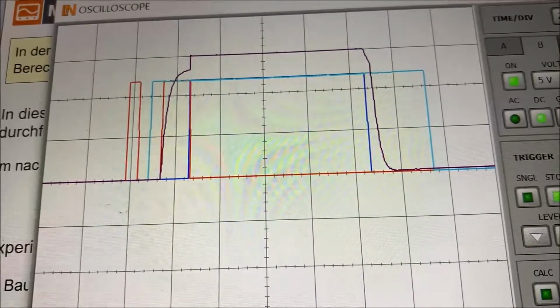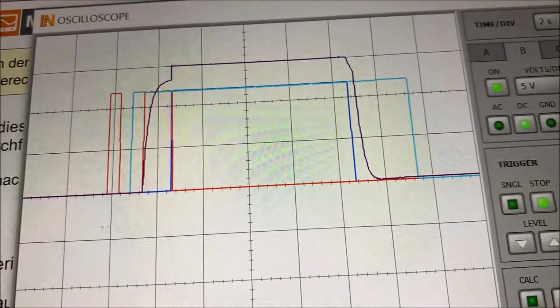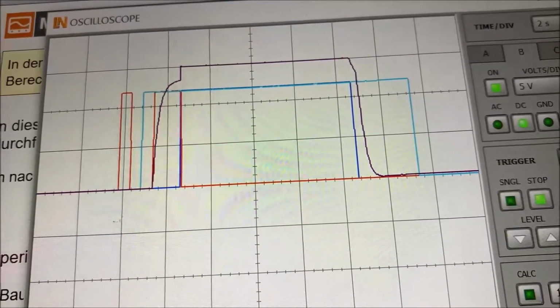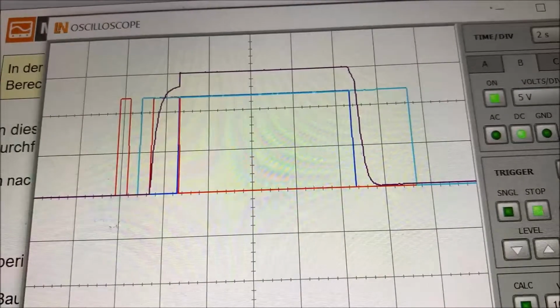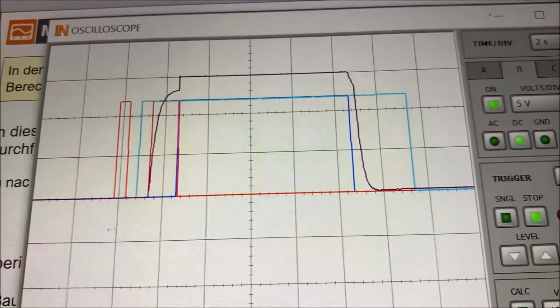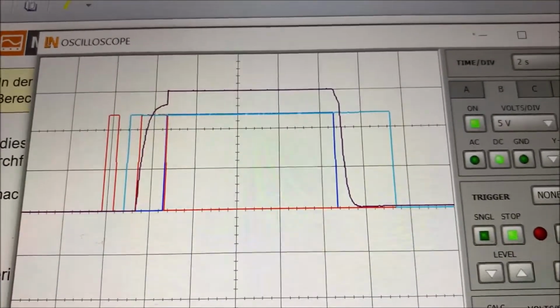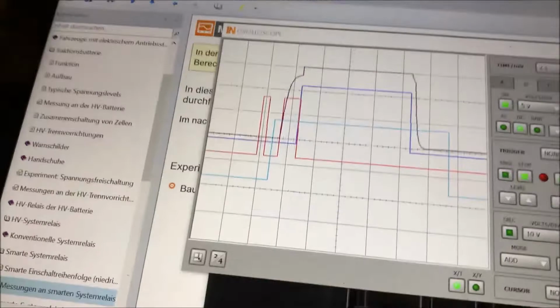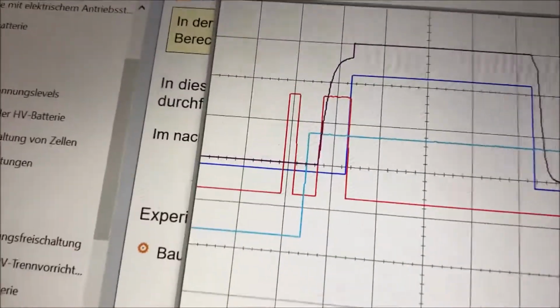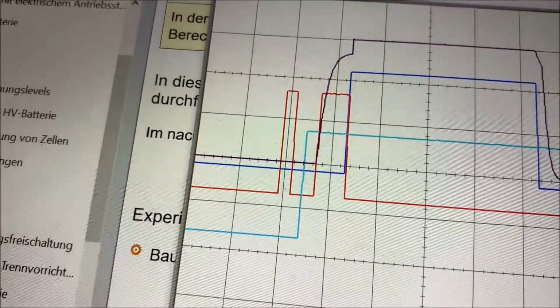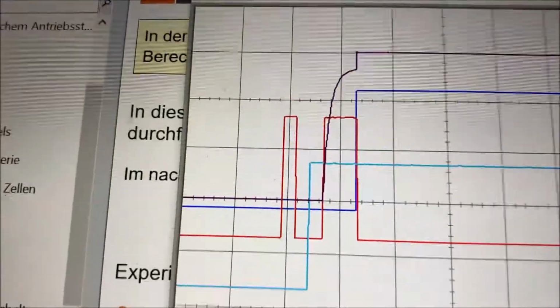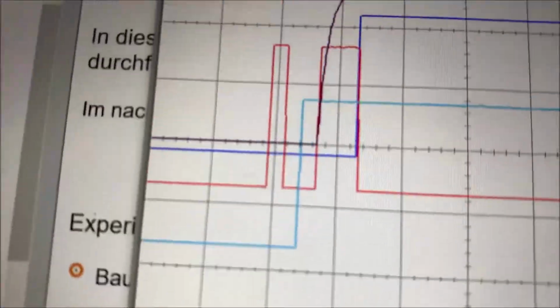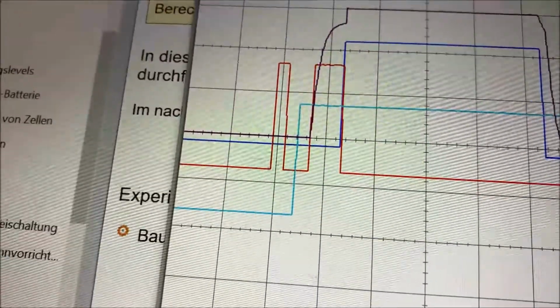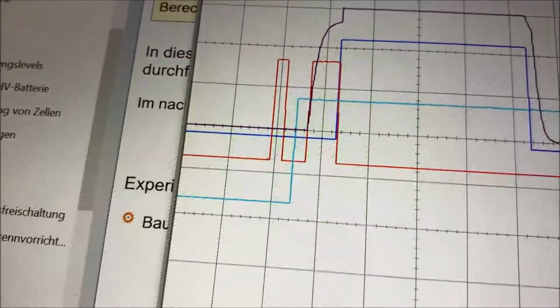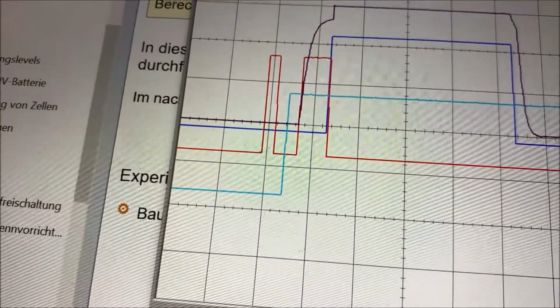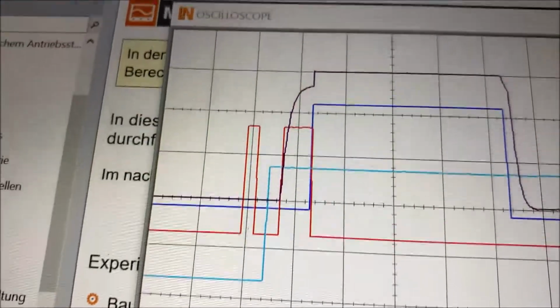Now you see that they are switching on and off multiple times. So you see the pre-charge relays coming up at different times, and also the high voltage minus relay, for example, is different in the times it comes on or switches off. So just let me drag it a little bit from each other. Okay, let's now have a closer look. You see that the pre-charge relay comes on first with no relay else. So this is basically in order to check if the high voltage minus relay, so this light blue one, is open or closed. It should be open, but when it's welded shut, so it's broken basically, and it would be closed, then you would get a high voltage signal.